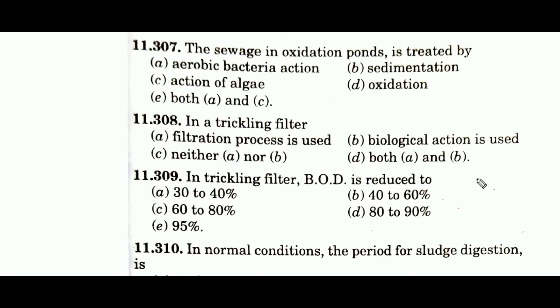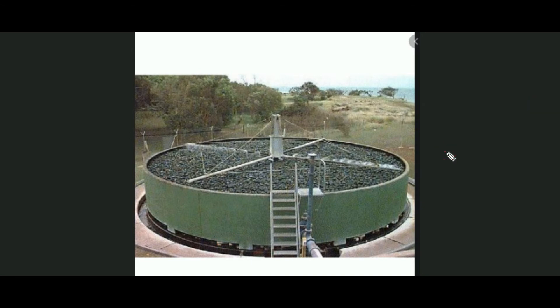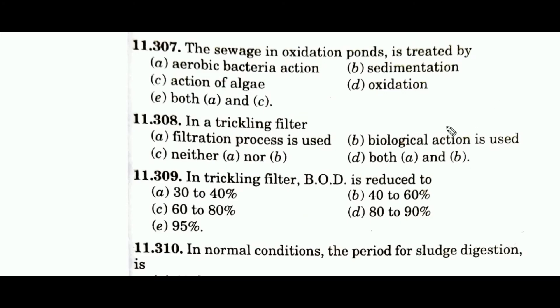Question 308 asks which process is used in a trickling filter — filtration or biological action. Both occur in a trickling filter. Filter media uses large-size aggregates. Sewage is applied through sprinklers at a very low rate. Organic matter and microorganisms attach to the filter media, where aerobic decomposition occurs due to the large area and available atmospheric air. Clear water percolates through. Both filtration and biological action occur, so the answer is option D.